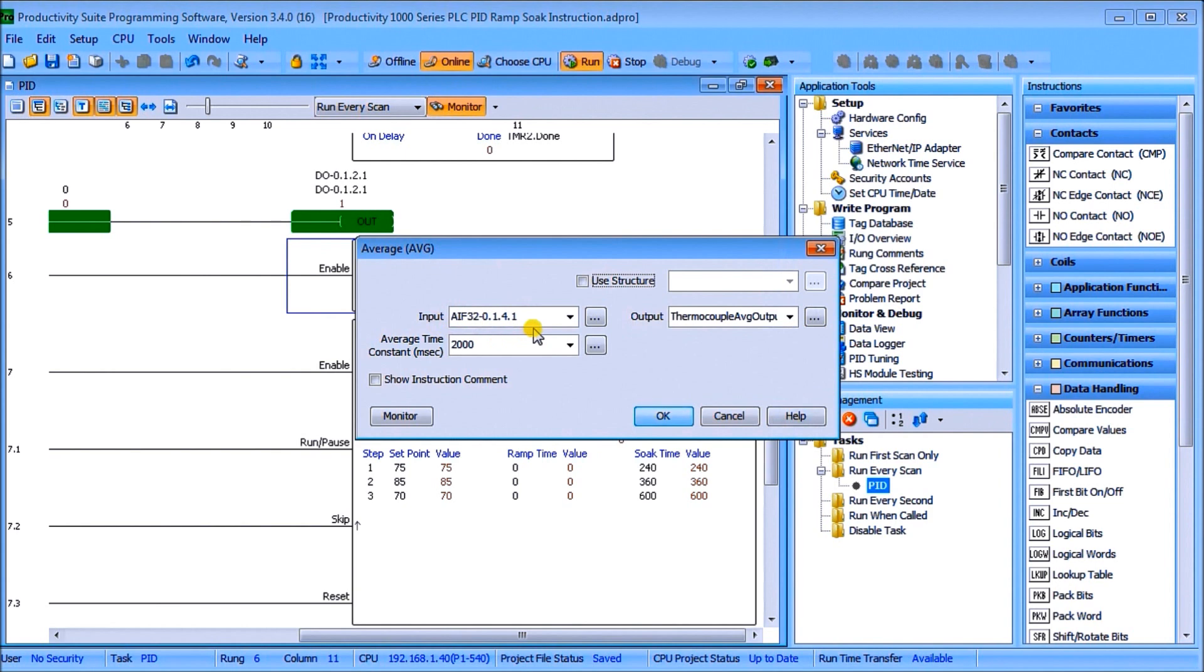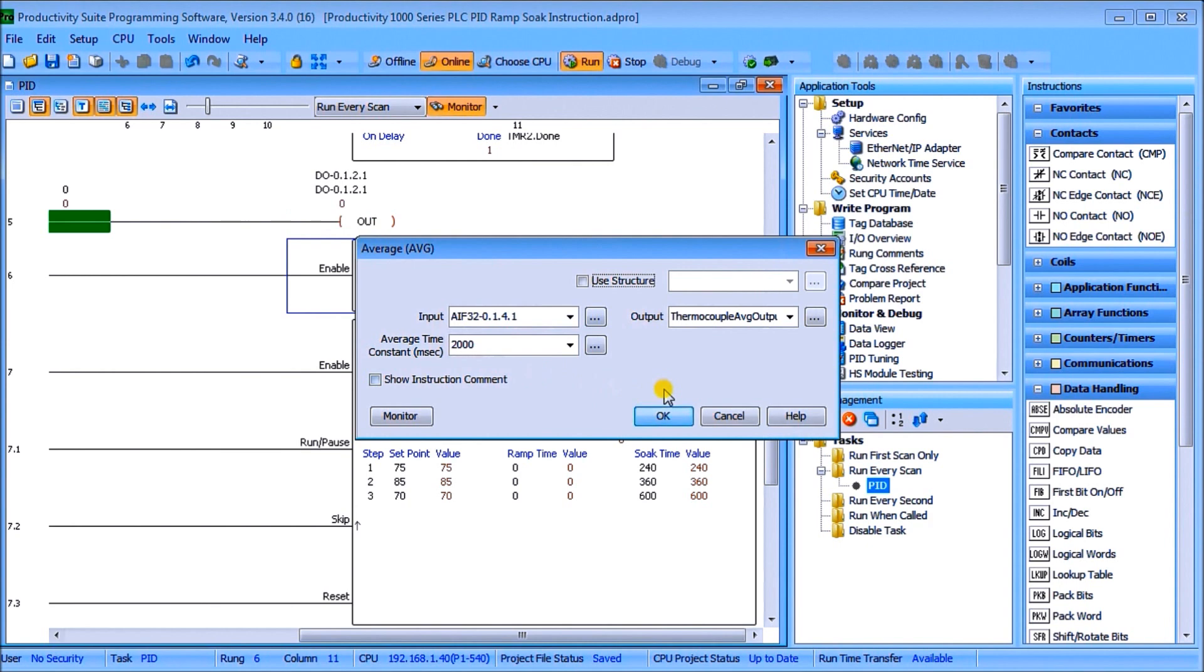So what we've done is we've taken the average of our input from our thermocouple and we put it on the thermocouple average output and we set that for two thousand milliseconds which is two seconds interval which is the same output as what our time proportional relay is actually oscillating at over the control period of that relay.